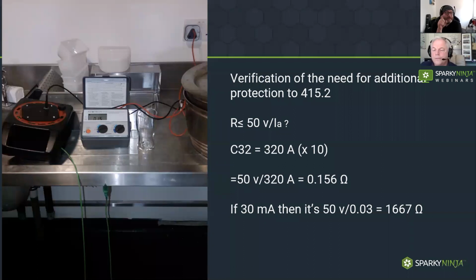In this case, with this socket, that value of resistance I measured - and you can see how easy it was to measure - was bang on the money if there was no RCD. I can't actually remember if there was an RCD, to be honest, but it's fine because it's bang on the money. If that resistance was any higher, the voltage is going to start to climb.